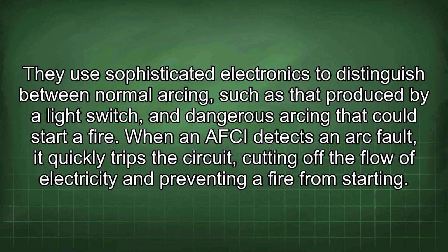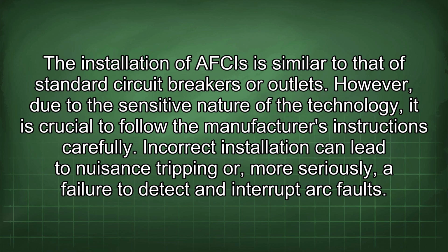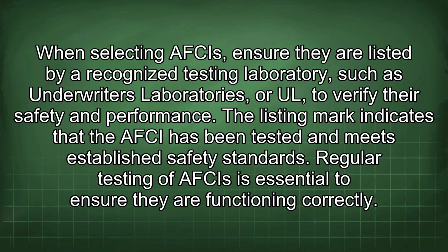When an AFCI detects an arc fault, it quickly trips the circuit, cutting off the flow of electricity and preventing a fire from starting. The installation of AFCIs is similar to that of standard circuit breakers or outlets. However, due to the sensitive nature of the technology, it is crucial to follow the manufacturer's instructions carefully. Incorrect installation can lead to nuisance tripping or, more seriously, a failure to detect and interrupt arc faults. When selecting AFCIs, ensure they are listed by a recognized testing laboratory, such as Underwriters Laboratories, or UL, to verify their safety and performance. The listing mark indicates that the AFCI has been tested and meets established safety standards.